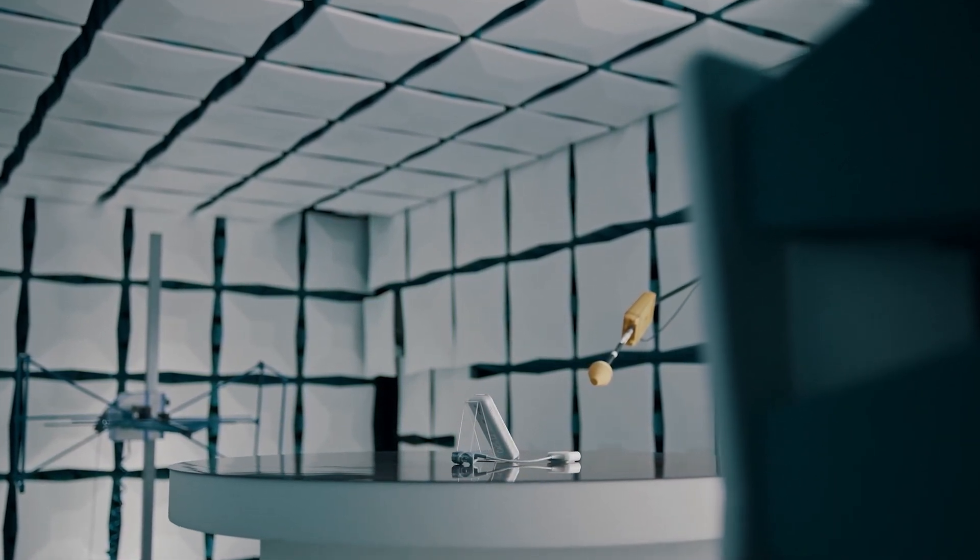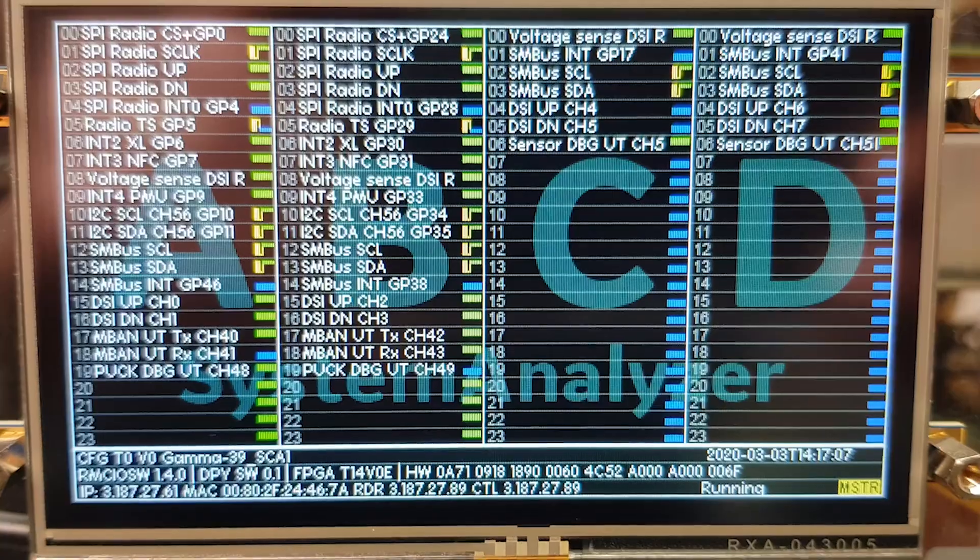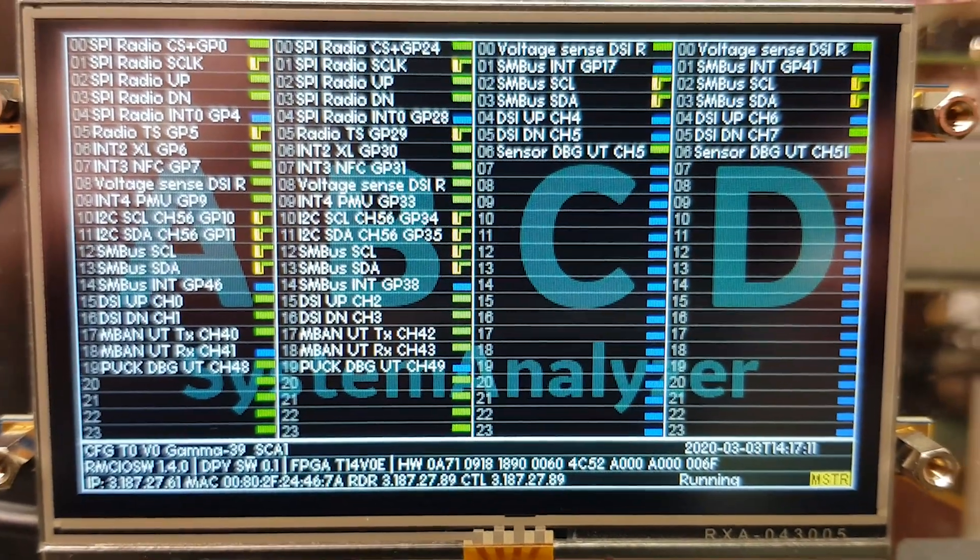We developed the MBAN communication technology — a body area network technology — which communicates data wirelessly from the sensor to our patient monitor. We designed a protocol that is deterministic in the way it moves from frequency to frequency and retry to retry, giving us the highest probability of getting data from point A to point B. That is unique, proprietary technology from GE Healthcare. The MBAN communication protocol was designed to be reliable — as good as a wired connection — and to be what we call a good citizen on the network.